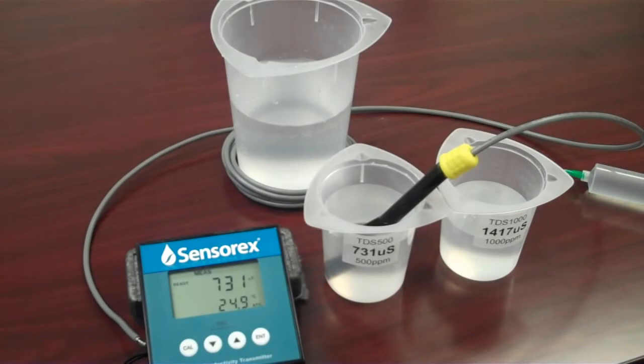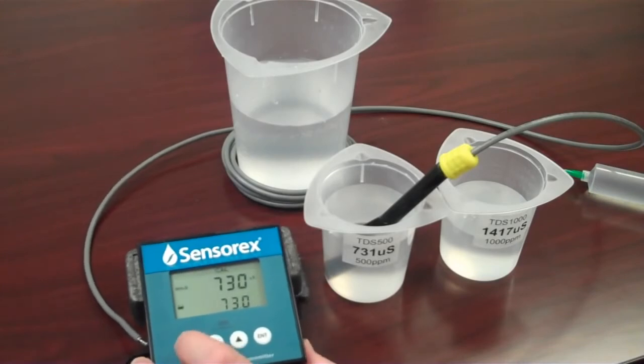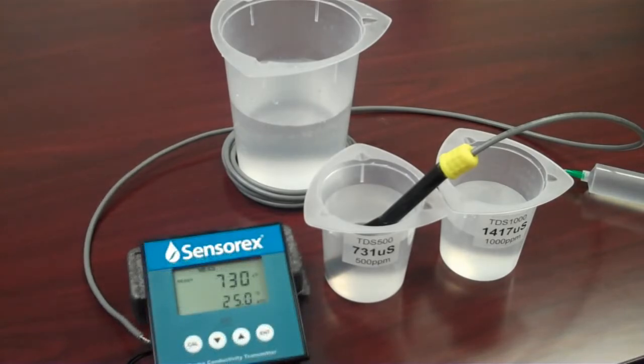To perform the conductivity calibration, we press the calibration key to enter calibration mode. The display will flash for a minute until it stabilizes. Use the arrow up and down if necessary to confirm the calibration value and return to the measurement mode. It's a good idea to check your calibration using a second conductivity standard.